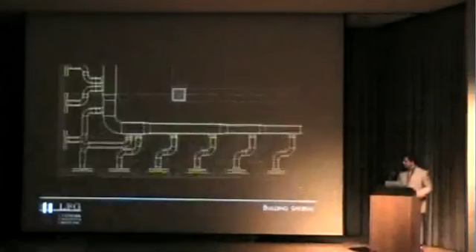In addition, each one of these branch ducts that feeds the perimeter has a balancing damper. But balancing dampers historically have a great deal of noise associated with them as they add resistance to the air. As they close, you get a lot of air turbulence around them, which causes noise. That air noise gets absorbed by two elbows, which were designed in, and we did go back and forth a number of times with the contractors, who eventually relented, but they were questioning why they couldn't just do a straight run into the duct here.